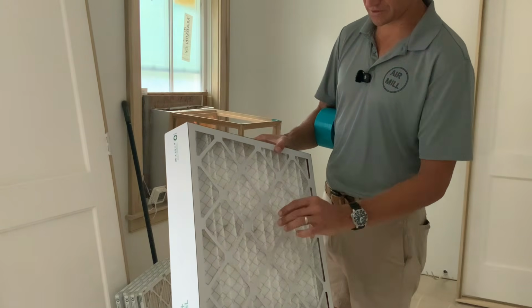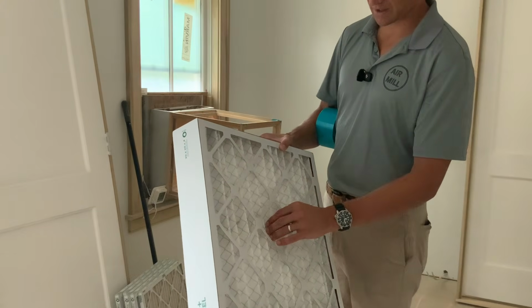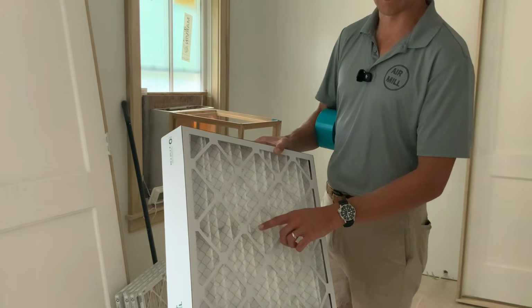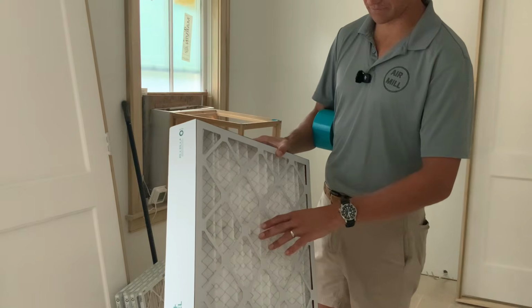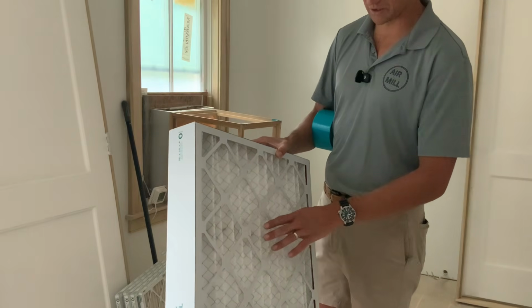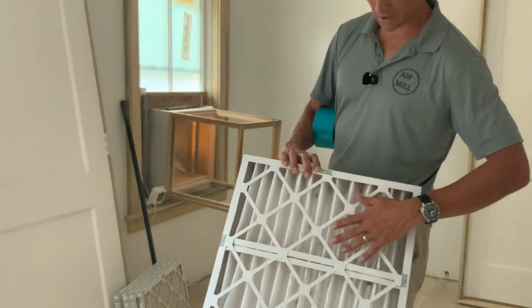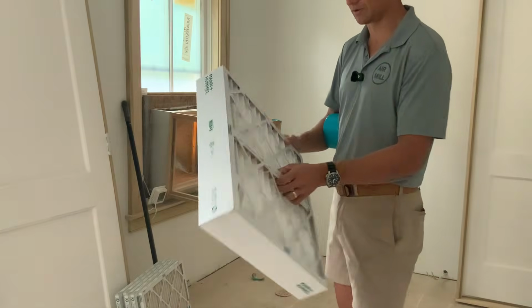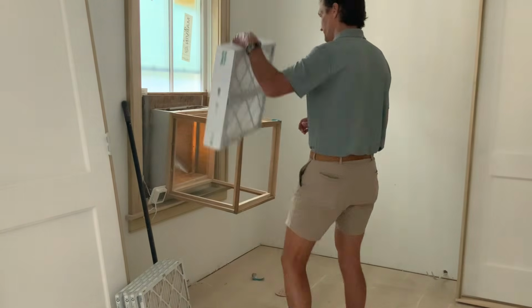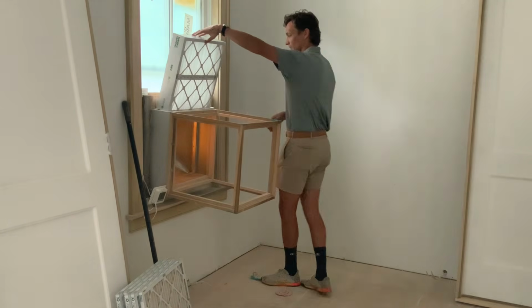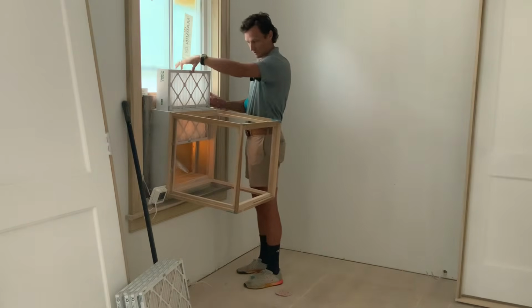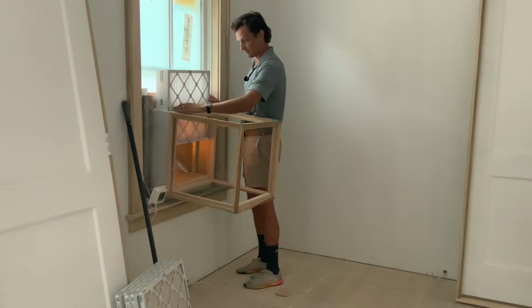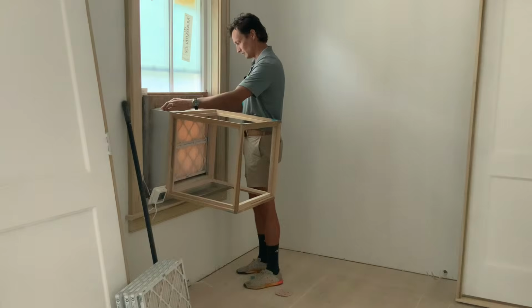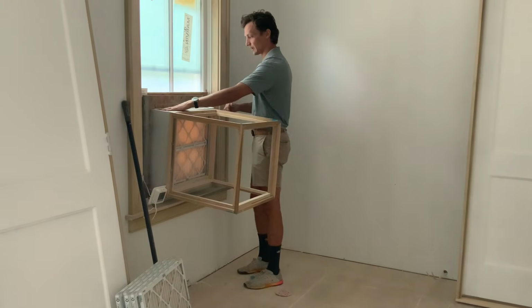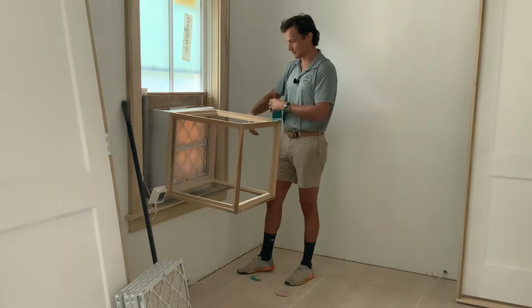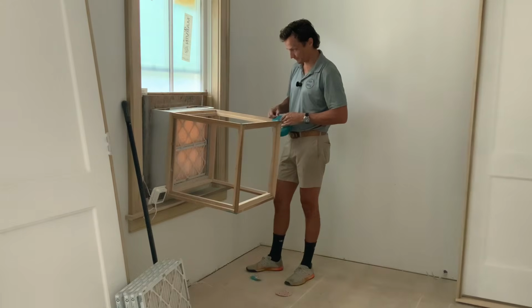This metal mesh helps support the fabric, but this metal mesh will also cut you badly. If you scrape your knuckles on this stuff, it can really get you bad. So be careful with that. This side faces out so that the metal supports it from behind. There's also airflow arrows on the filters, but that's why the airflow is important, to have that metal facing in towards the machine so it supports the filter.